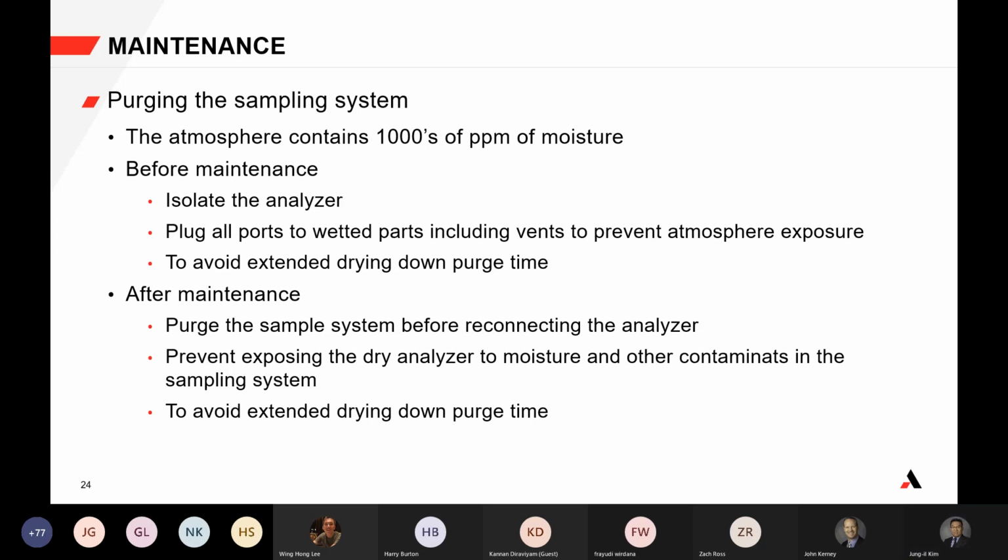Whether the analyzer can handle back pressure and how it handles it is dependent on the different technologies. For example, QCM analyzers are first designed to be vented to atmosphere, but due to hazard conditions where the analyzer has to vent to a flare that is pressurized, we don't want back pressure, all the junk in the exhaust system, going into the analyzer.